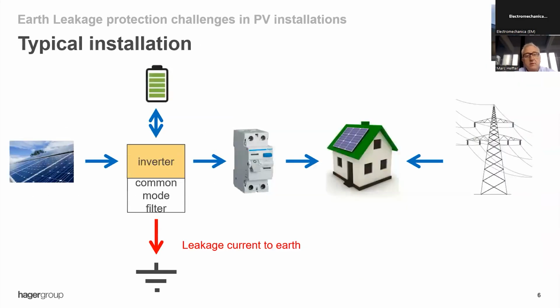This is a typical installation. We have the PV installation, the inverter, the RCCB, the building and the grid. The problem occurs when the grid disappears. You are powering the house off-grid, disconnected from the grid. And when the grid comes back, there is some tripping of the RCCB.